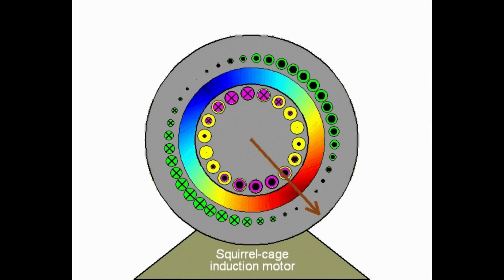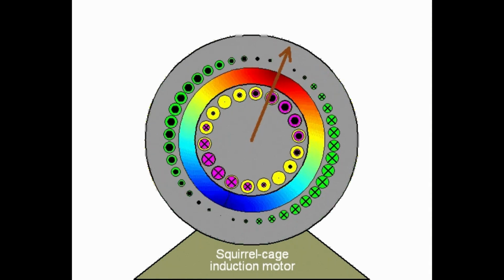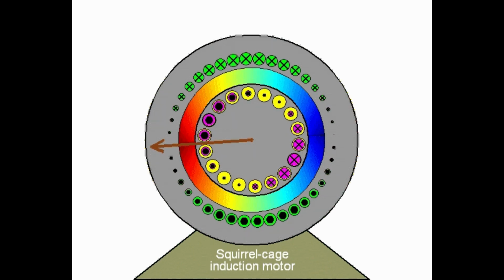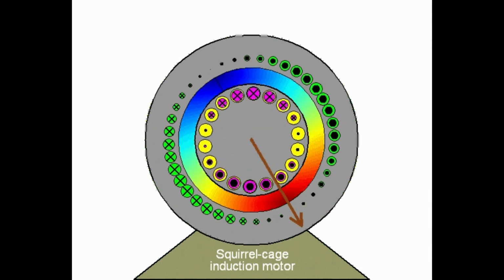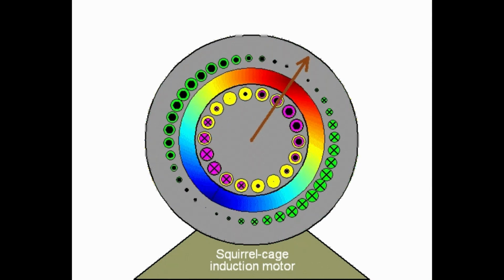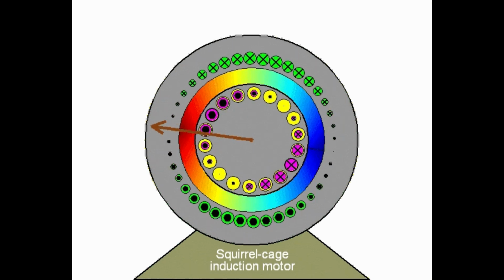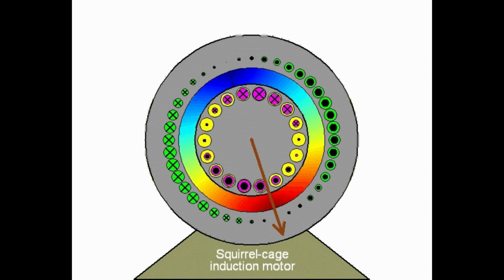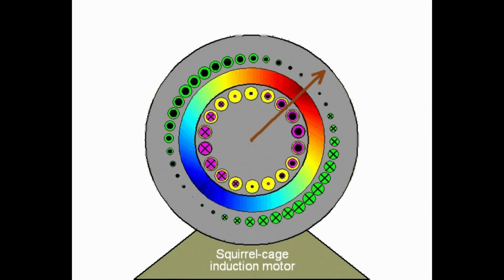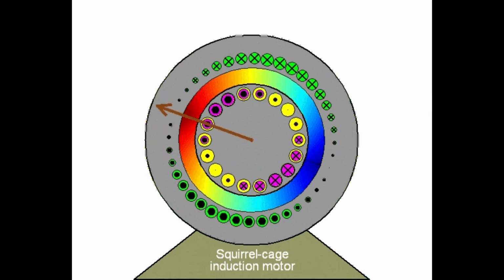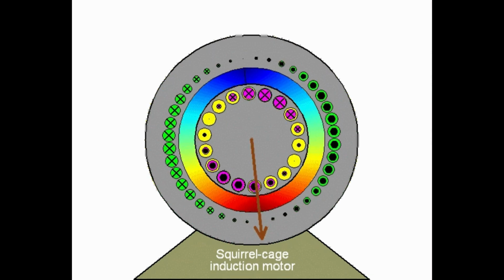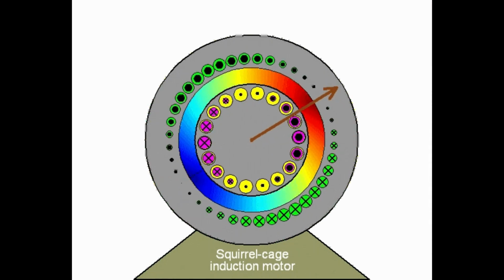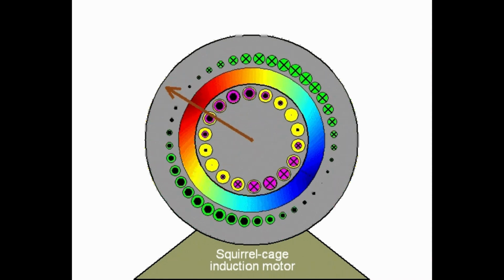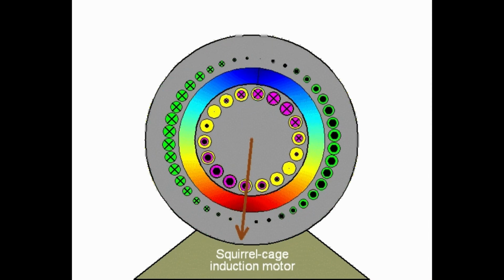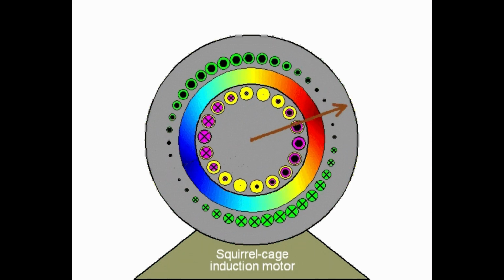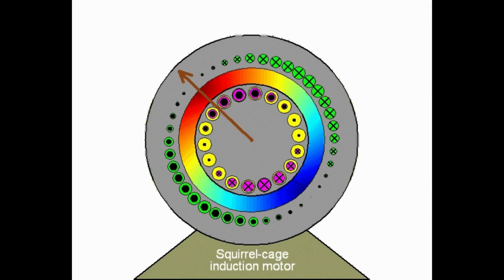An increase in the line voltage causes a decrease in the slip, and a decrease in the line voltage causes an increase in the slip. In either case, sufficient current is induced in the rotor to carry the load. A decrease in the line voltage causes an increase in the heating of the motor. An increase in the line voltage decreases the heating. In other words, the motor can carry a larger load. The slip at rated load may vary from 3% to 20% for different types of motors.